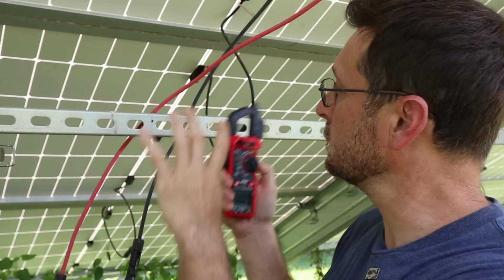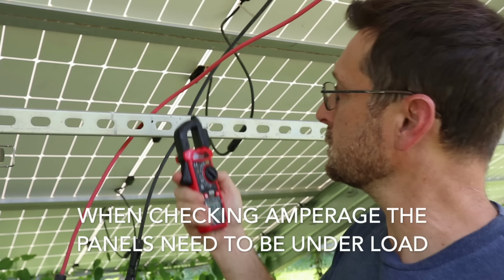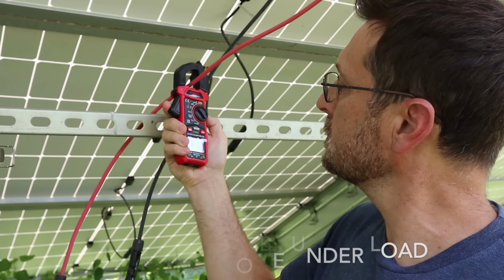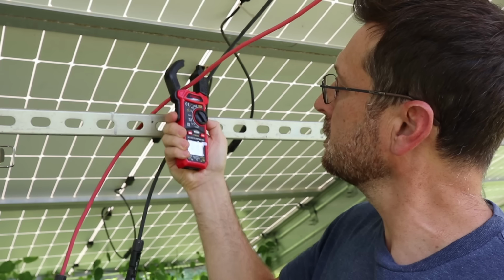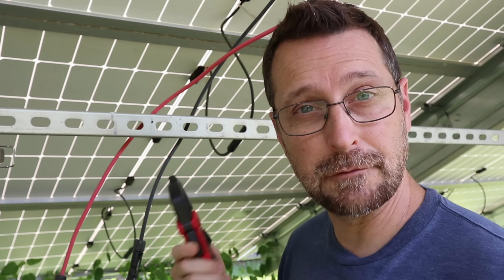But let's put this on one of our PV conductors and see if there's an issue that way. Now I'm going to come over here to the positive and negative of one of my strings. I'm going to look at the amperage. This one is about 8, and this one is -8. You want to try to do this in full sun so you can get a good reading.